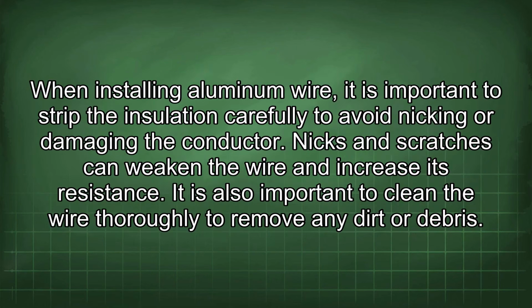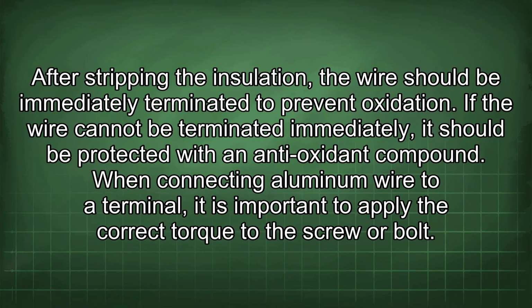When installing aluminum wire, it is important to strip the insulation carefully to avoid nicking or damaging the conductor. Nicks and scratches can weaken the wire and increase its resistance. It is also important to clean the wire thoroughly to remove any dirt or debris. After stripping the insulation, the wire should be immediately terminated to prevent oxidation. If the wire cannot be terminated immediately, it should be protected with an antioxidant compound.